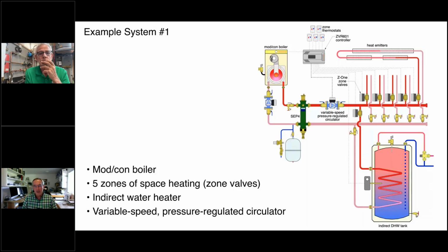I don't really want to take a lot of time on them, but these are all in Hydronics 36 that'll be coming out in the near future this fall. And they're all examples of zoning. So we've got a basic system with a ModCon boiler, zone valves doing space heating. We've got a zone valve doing an indirect water heater. We're using the SEP4 to isolate the flow dynamics of the variable speed pump from the boiler. So really simple, very common system.